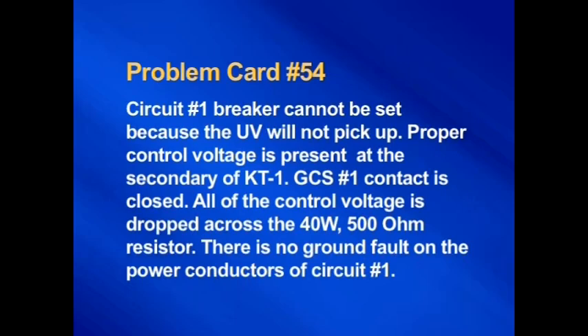The next problem card. Problem card number 54. Circuit number 1 breaker cannot be set because the UV will not pick up. Proper control voltage is present at the secondary of KT1. GCS number 1 contact is closed. All of the control voltage is dropped across the 40 watt 500 ohm resistor. There's no ground fault on the power conductors of circuit number 1.